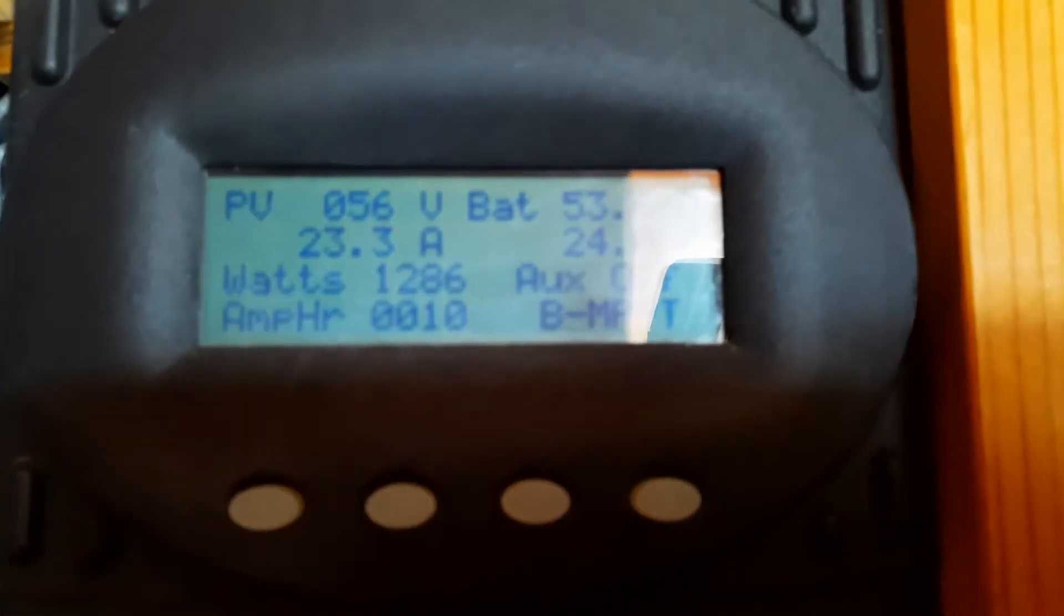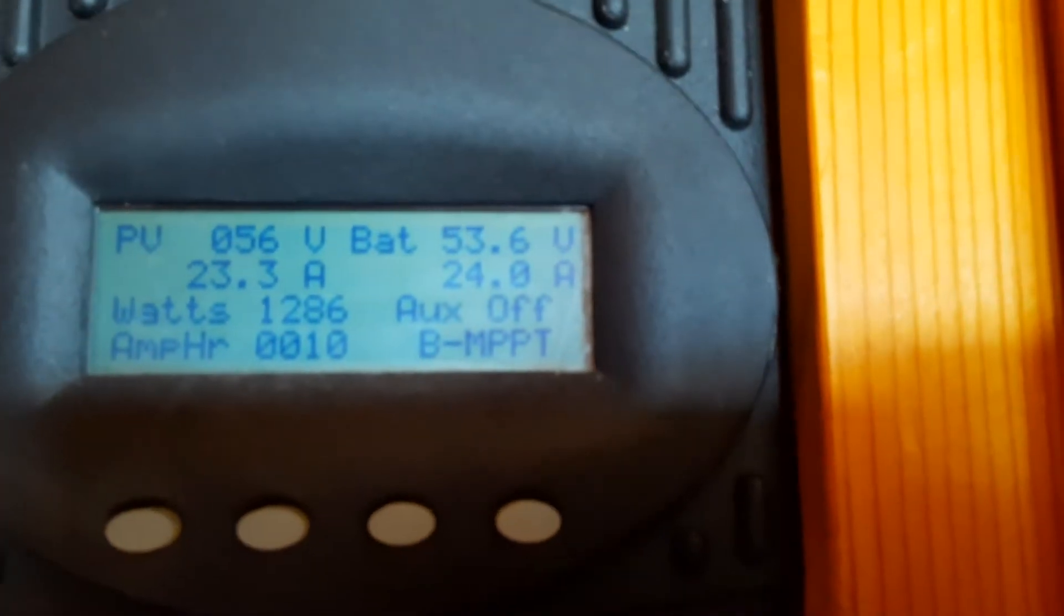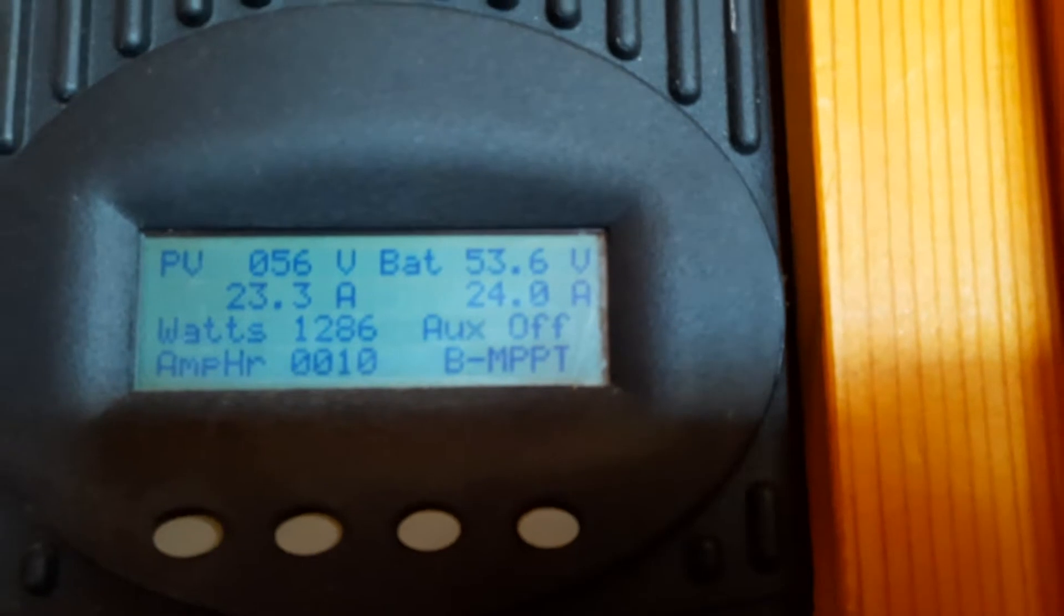Array voltage 56 volts, battery voltage 53. That's probably the source of the alarm. I don't know why it dropped as 56 like that. It was at 60 or 61 volts, it seemed to be happy at that voltage.